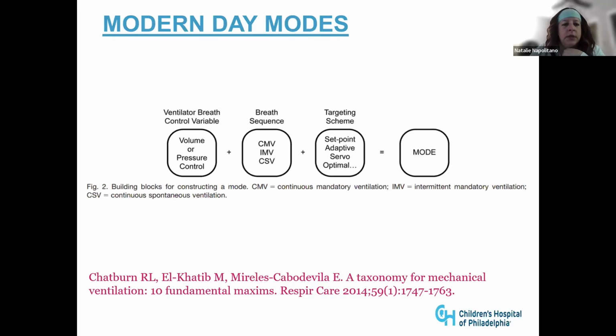So it's even the naming schemes that you have from the manufacturers, you need to kind of dig in this way to figure out what type of breath it is and what the targeting scheme is. The most common mode that everybody says to me is, I want PRVC. Well, if I don't have a servo ventilator, I can't give you PRVC because that's trademarked to Maquet.